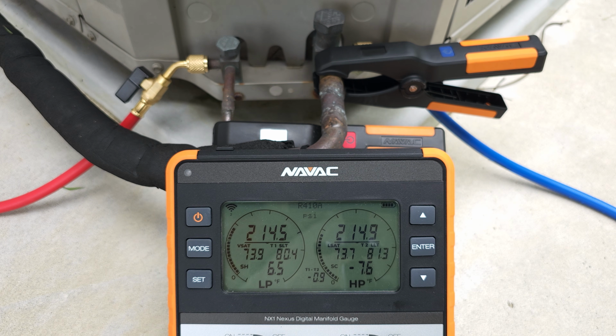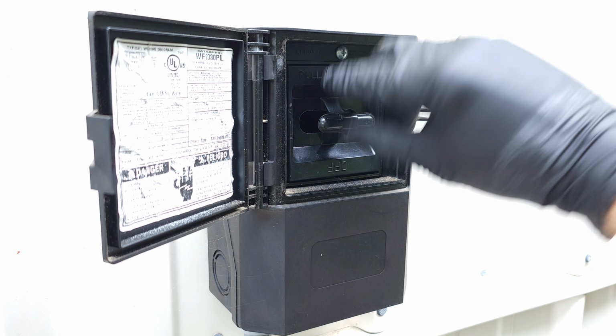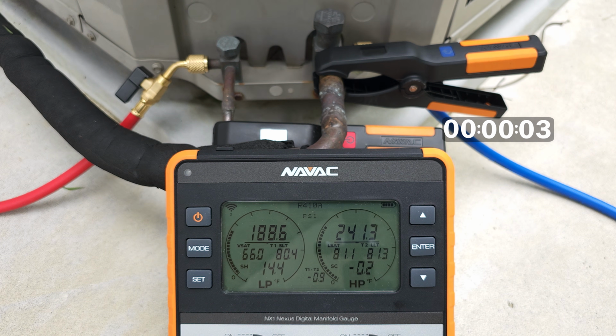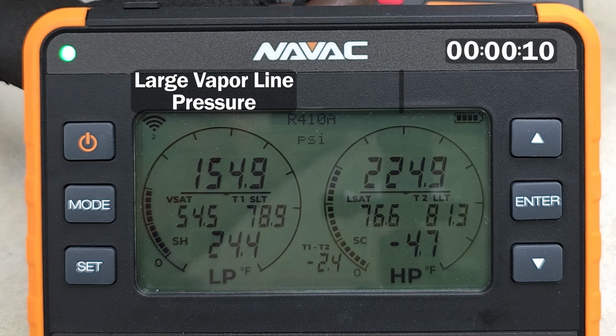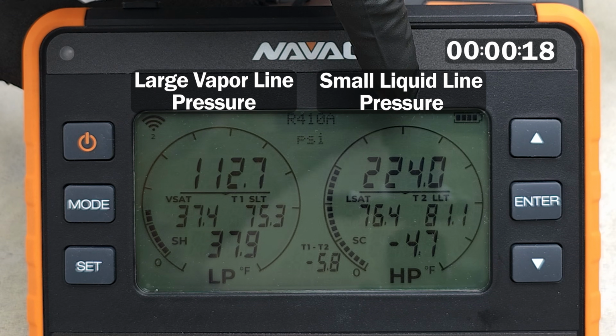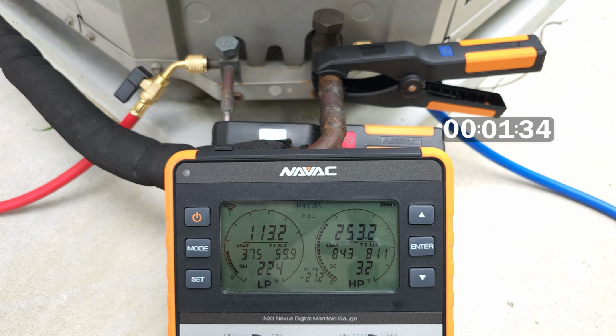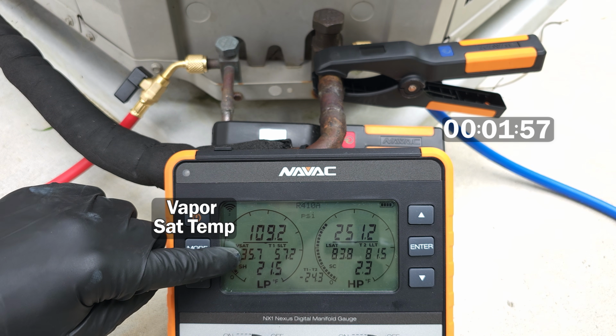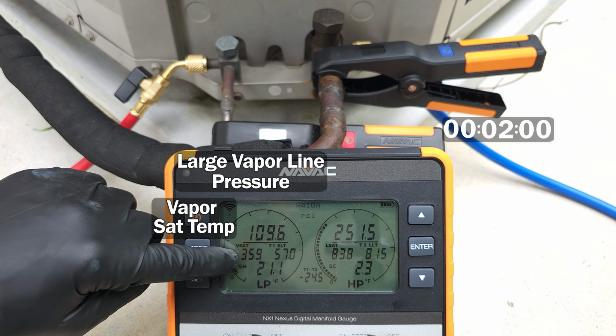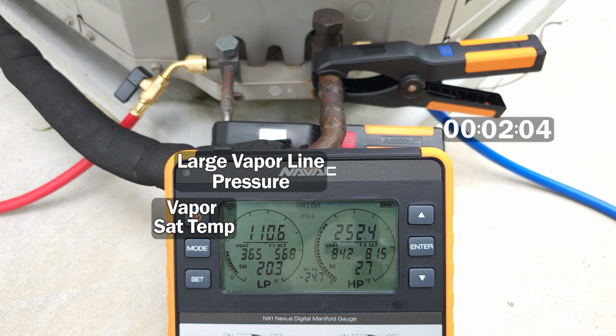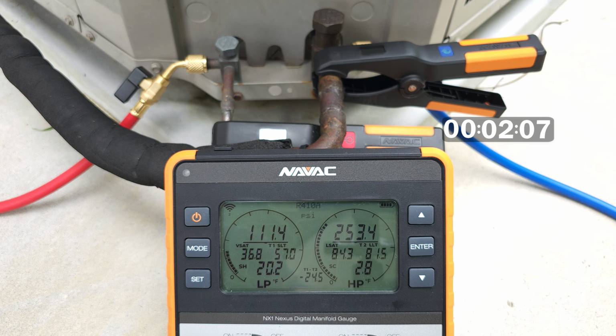Now we're going to turn the unit on at the outdoor disconnect. We're going to give it a little bit of time. You want to wait about 5 to 10 minutes before measuring the refrigerant charge or doing troubleshooting with the refrigerant charge measurements in order for the refrigerant to cycle through the system. You're noticing our vapor saturated temperature is continuing to lower. So our pressure is lowering, which means our saturated temperature is lowering. But we want to give it, say, 5 to 10 minutes before accurately measuring these pressures and temperatures.